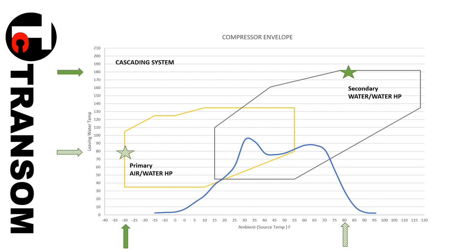We did one project for a school in Joliette, Quebec, a technical school, and they had gas boilers. One of the things in Quebec is they have very low-cost electrical power, and gas is very expensive, so they were trying to do away with the gas boilers. They put in water source heat pumps. They dug up the football field, and that was their loops for the source. But it was still only so big, so our source temperature was 28 degrees, and we generated 160 degree water. At that time, getting to 180 wasn't much available. So we generated 160, and they worked out that they could heat the school with 160 instead of the traditional 180. If you had a boiler and you do 180, you don't have to worry about it, right?